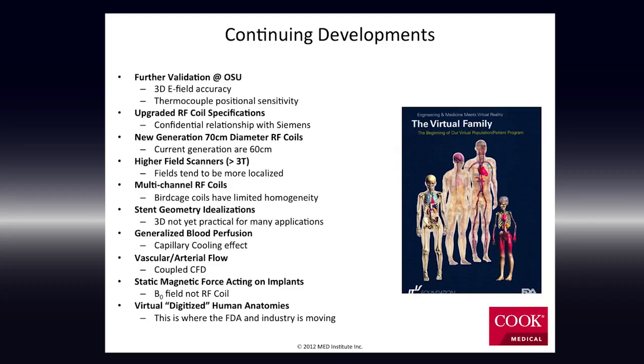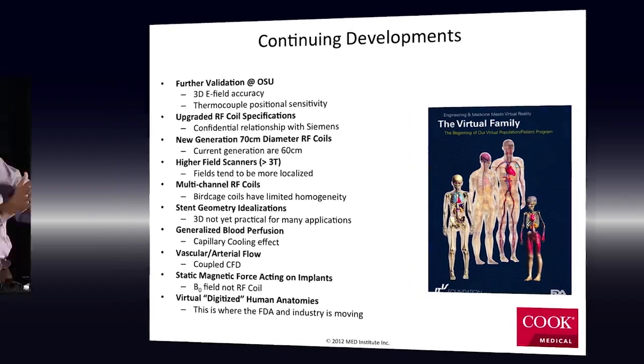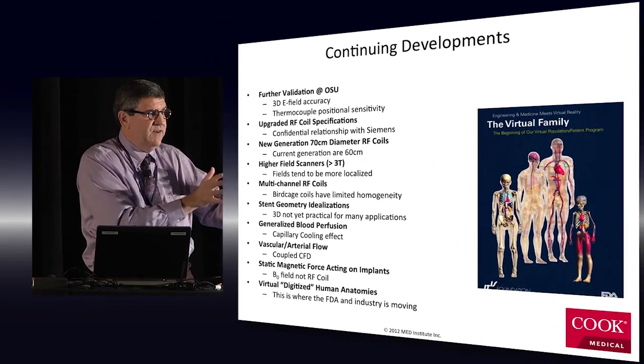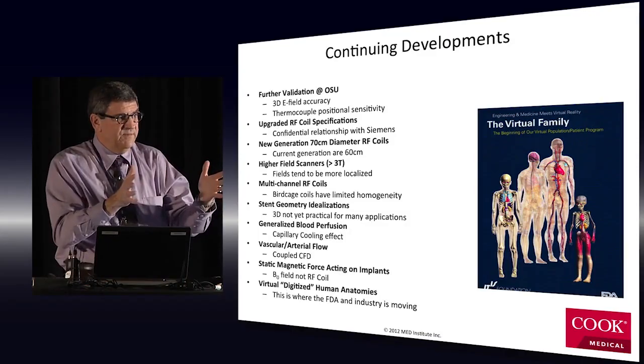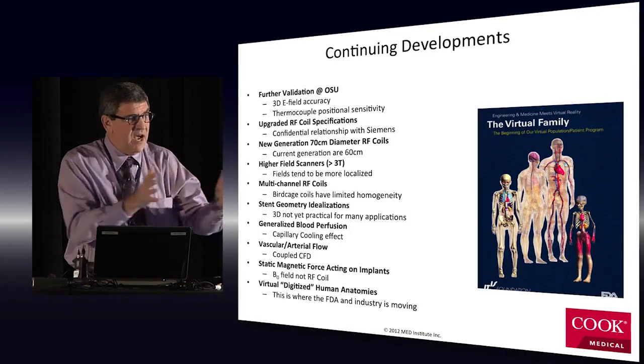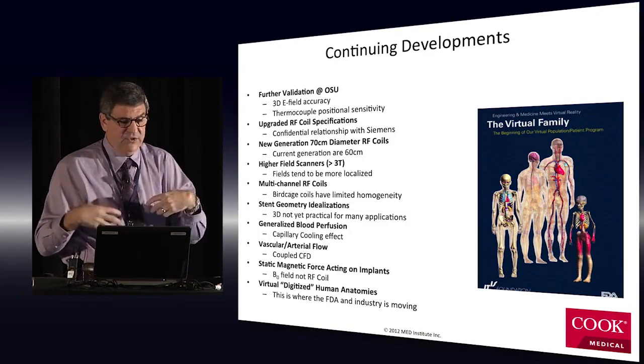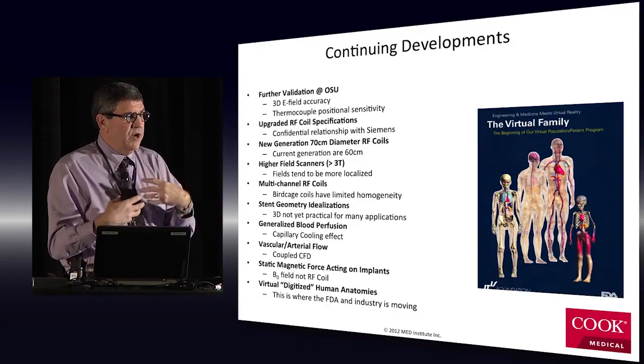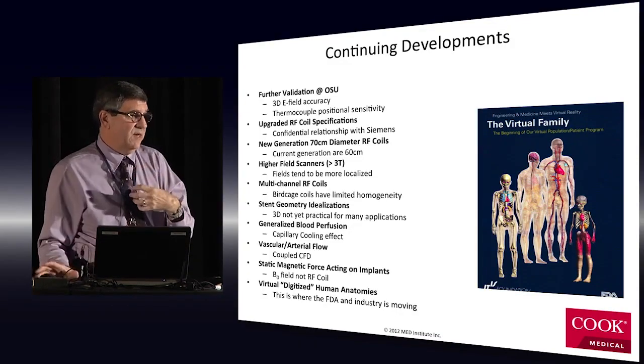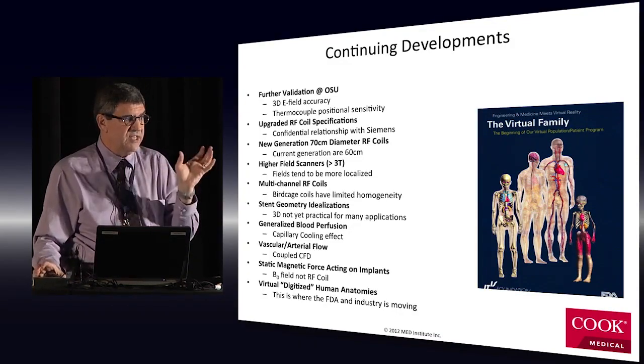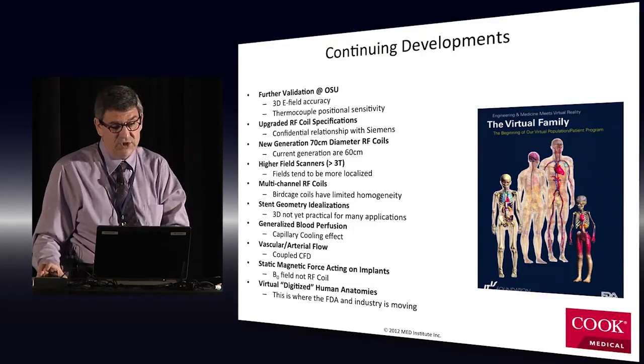But there are stainless devices that we manufacture, especially stent graft devices, and you want to know what the forces are in these devices. Even though the magnetic field is uniform in the center, so there's really no magnetic force on the devices, you have to pass through very near the point of the highest gradient of the magnetic field, so there are forces, and you want to ensure that your device doesn't migrate, and stays where it should and functions the way it should.